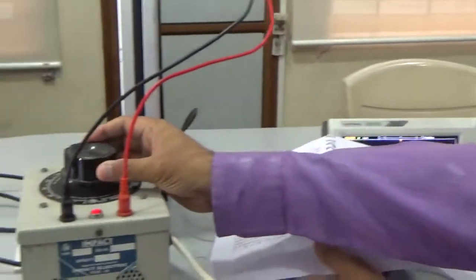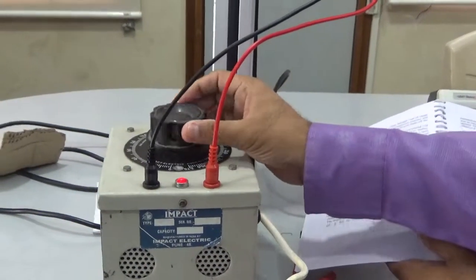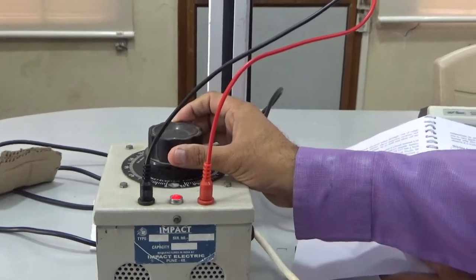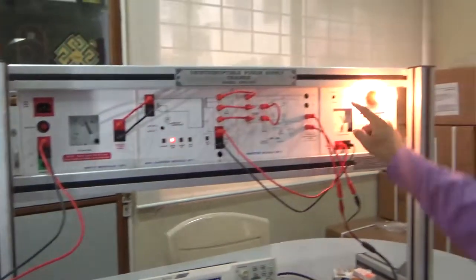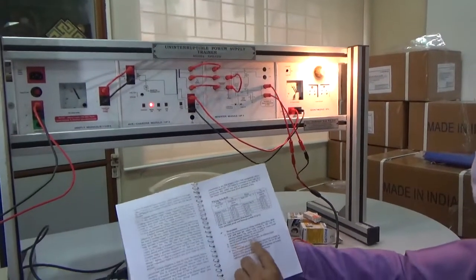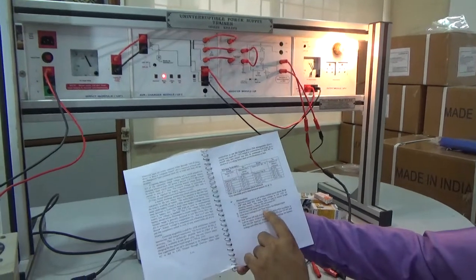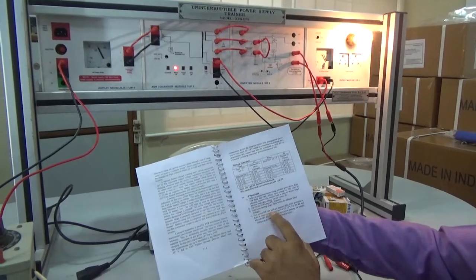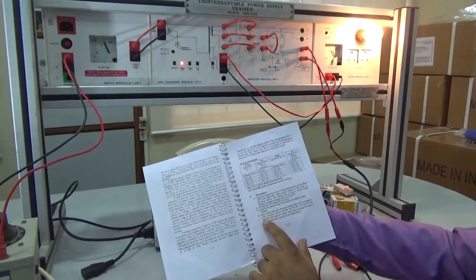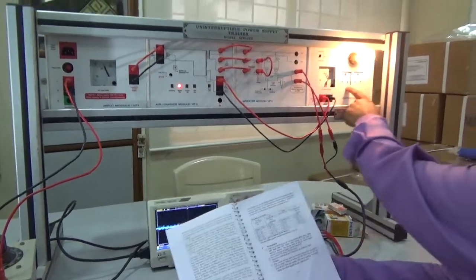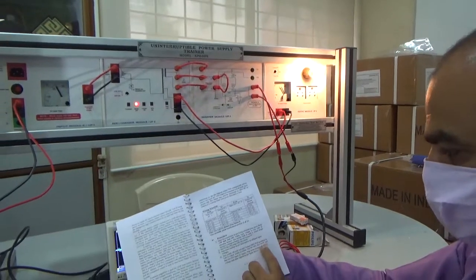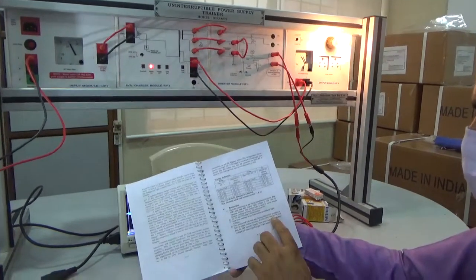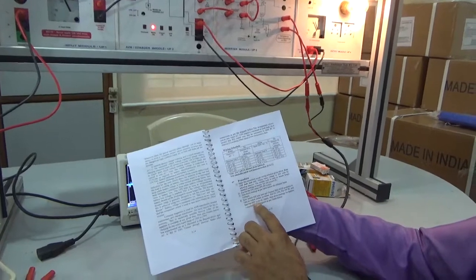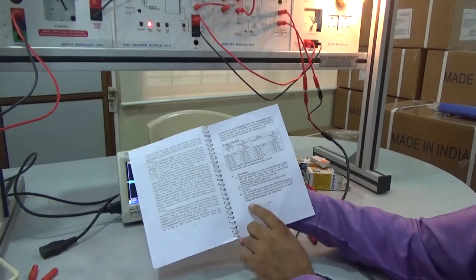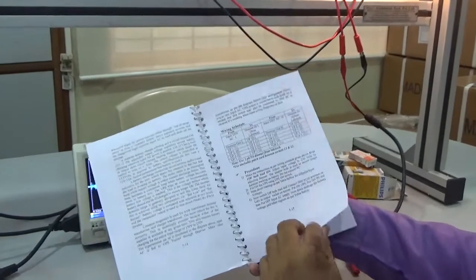First we will increase this to 230 volt. We'll make this UPS on switch. Note down the reading as per the table given. Now switch off the bulb load and connect an IBM PC, if available in the lab, to the output sockets given here. Put on the PC and then put off the AC supply. Note down the readings for battery voltage and other signals as per the table given below.